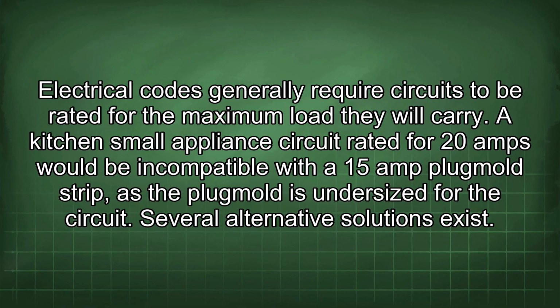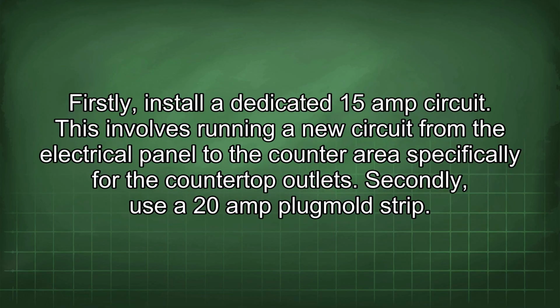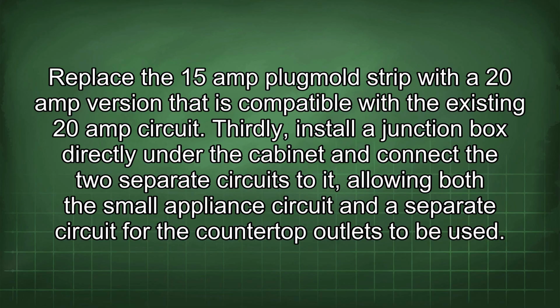Several alternative solutions exist. Firstly, install a dedicated 15 amp circuit. This involves running a new circuit from the electrical panel to the counter area specifically for the countertop outlets. Secondly, use a 20 amp Plugmold strip. Replace the 15 amp Plugmold strip with a 20 amp version that is compatible with the existing 20 amp circuit.